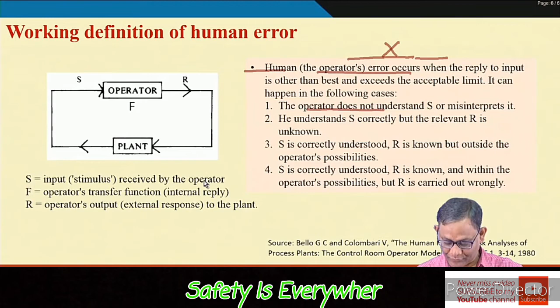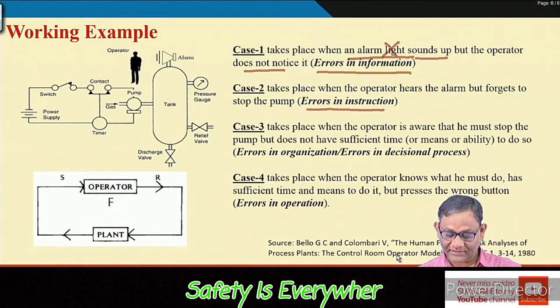So, second case, error in instruction. The operator hears the alarm, but forgot to stop the pump. Third case takes place when the operator is aware that he must stop the pump, but does not have sufficient time to do so. Error in organization, or error in the decisional process. So, he hears this, then checks the pressure gauge, and then goes for removing the contact, but this entire process takes more time. So, that is why the overpressure condition is not arrested.